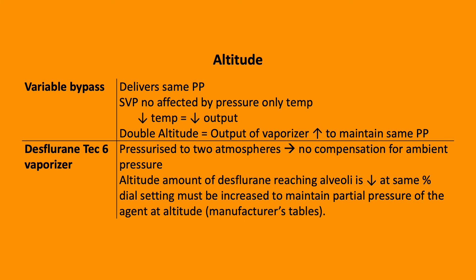Altitude and vaporizers: variable bypass vaporizers always deliver the same partial pressure, so theoretically they shouldn't be affected by altitude. However, there is a reduction in temperature at high altitude which reduces output — so if altitude doubles, the output increases to maintain the same partial pressure. This is different for the TEC6 vaporizer for desflurane. These are pressurized to two atmospheres with no compensation for ambient pressure. At altitude, the amount of desflurane reaching the alveoli reduces at the same percentage, so the dial must be adjusted to increase the concentration, and there are manufacturer tables to guide this.